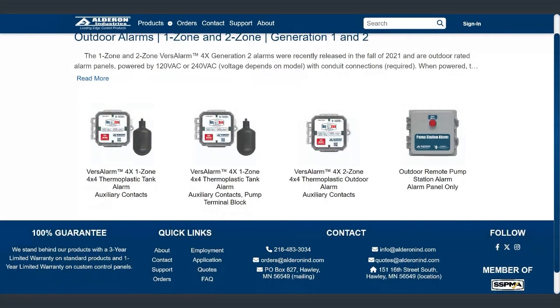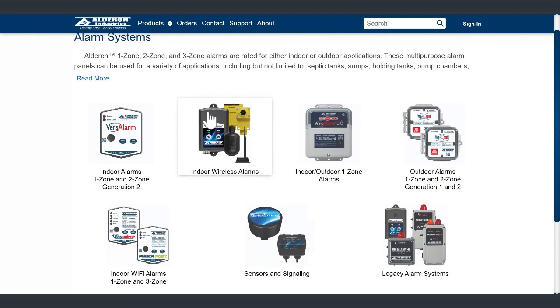So on that wireless alarm, this one, yeah. Can you send a pump run signal through that? So you can if you have, like on the contactors here, they have an auxiliary port, so you can just connect that to the transmitter instead. Yeah, to run signal. Yeah.